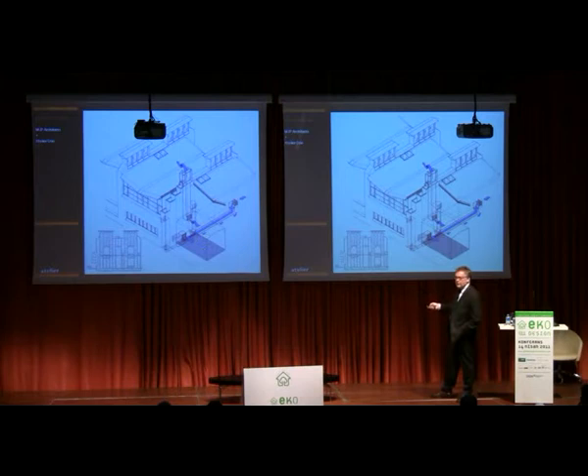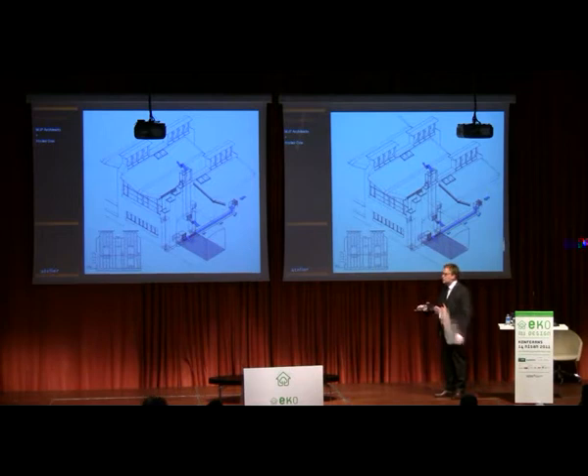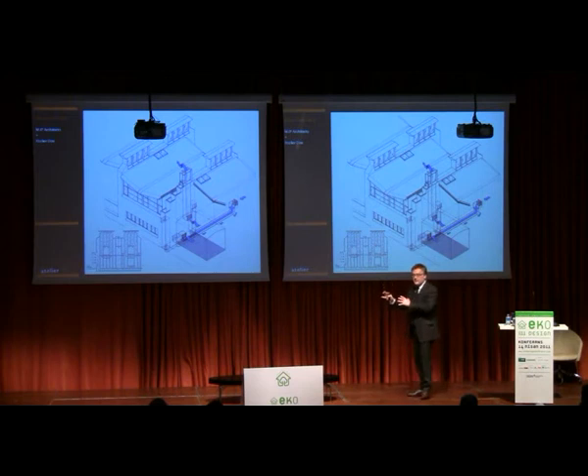It also allows us to do a very important thing: naturally ventilate the room at night in summertime. We can leave these vents open without compromising the security of the building, letting it breathe at night. The thermal mass of the building is cooled, and very securely it's allowed to ventilate. At the point when the building is cool enough, the dampers automatically close and the building is sealed up for the night. That building has been very effective.